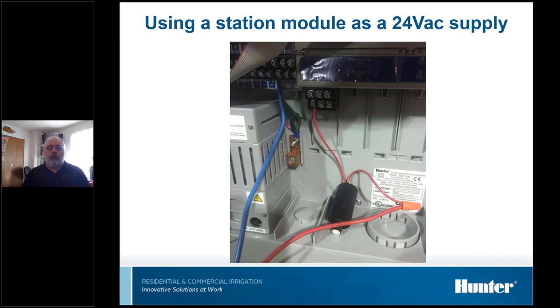There are just some other examples of some stuff we've come up with. They're in a pinch work. This is an ACC controller, and we just took the decoder module out and put a conventional station module in there, and then we can just turn a station on to be our 24-volt supply. If you do this, you definitely need to put the solenoid in line, because that module is only capable of about 3/4 of an amp. If you put it in there and you're drawing over an amp, it'll just fry the module, and then you really didn't accomplish anything.